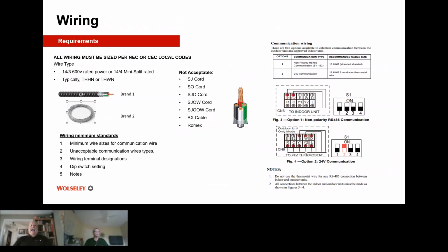As I was alluding to about wiring earlier, please make sure we use the appropriate wiring, that it meets the electrical code or the local code in your area. As I said, these are just some forms that are not acceptable. I have been to many job sites where building owners or building contractors have put these units in and have run BX cable or Romex, and they wonder why their units don't work. Or when a service technician comes to start them up, they don't work. It's because they put the wrong electrical wire in. We want to make sure that we put the right conduit in there, that it is rated for our units and that it is the right size.